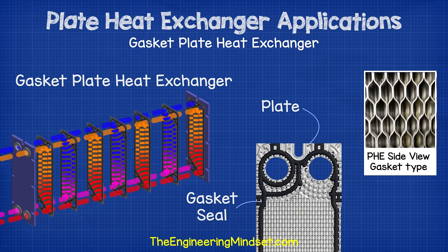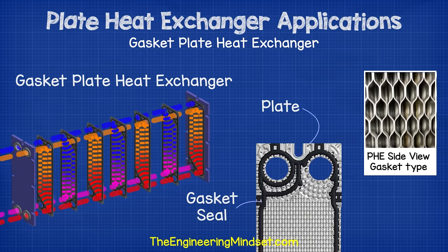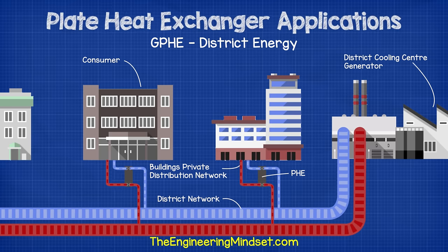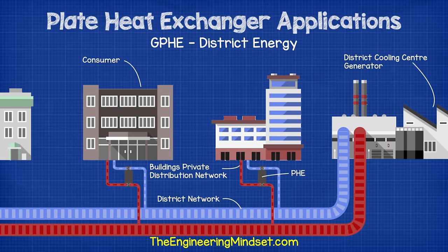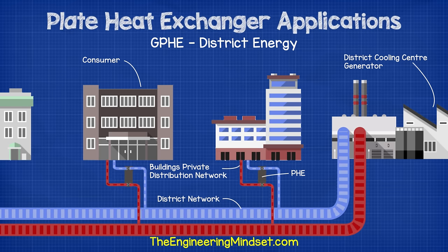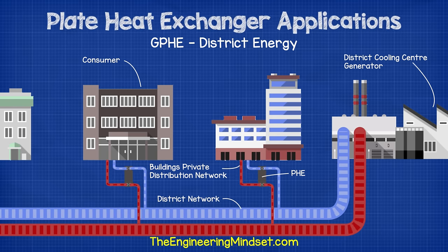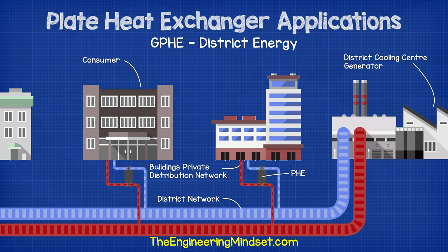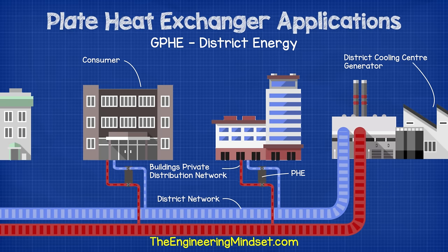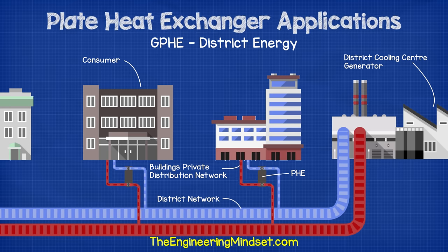Applications of gasket plate heat exchangers — you'll find these in many heavy-duty HVAC as well as industrial and process engineering applications. For district heating and cooling, these heat exchangers are used to connect buildings to district heating and cooling networks. The district center distributes hot and cold fluids around central pipes, and buildings connect to these networks via gasket plate heat exchangers installed between the building's central plant circuit and the district network, usually through a heat meter to measure consumption.